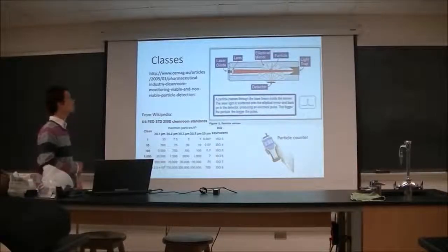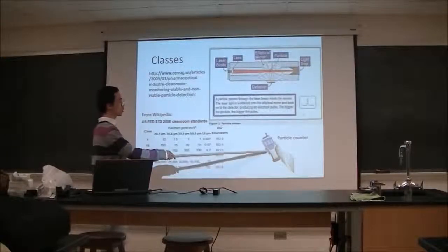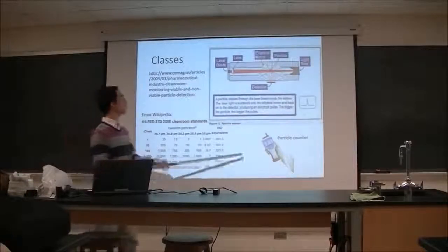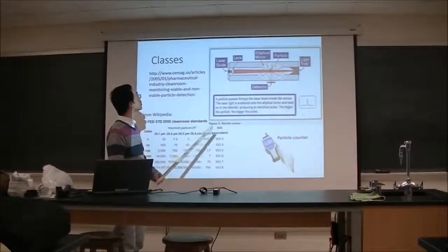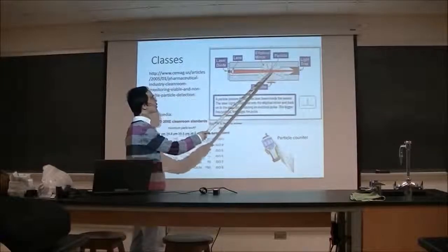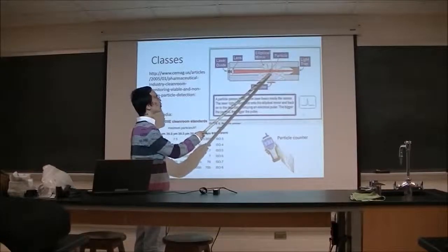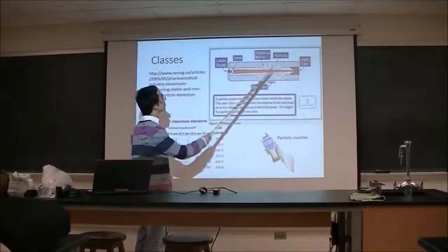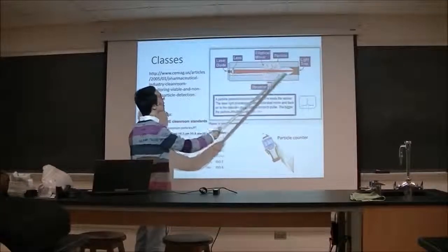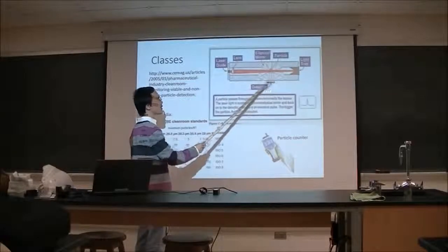numbers of the particles? Normally you just use a particle counter. It's really small. You can install several of them in your clean room, or you can use this handheld one. The principle is simple. You have a laser beam shooting into a chamber, and in this chamber you have air from the clean room. There you have different types of particles. So these particles will reflect light to a mirror, and all the light will be collected to a detector, a light detector.